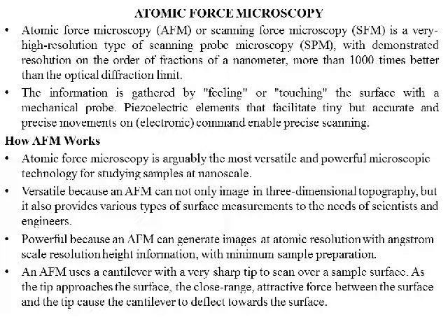So what are the different elements of this AFM? AFM uses a cantilever, as we discussed in SPM. Here also we have a cantilever with a very sharp tip at the bottom. This sharp tip is also called a probe. This tip will scan the sample surface. When the tip approaches the surface, it will touch the surface of the specimen, and the attractive force between the surface of the specimen and the tip of the cantilever will deflect the cantilever because of the waviness or the ups and downs of the surface roughness of the specimen.